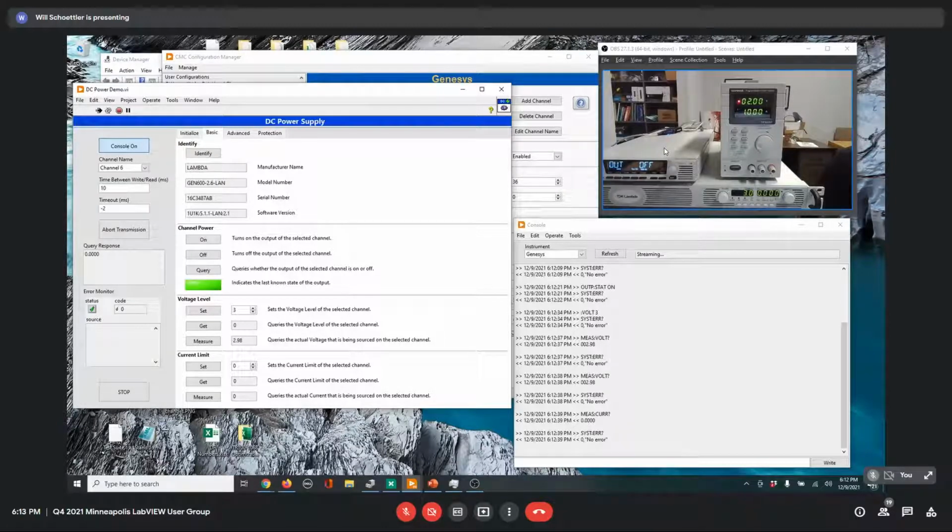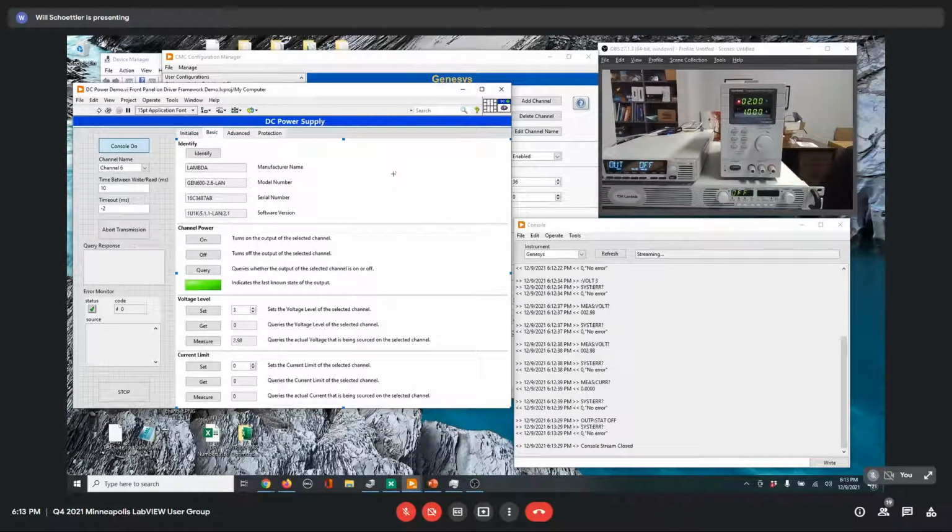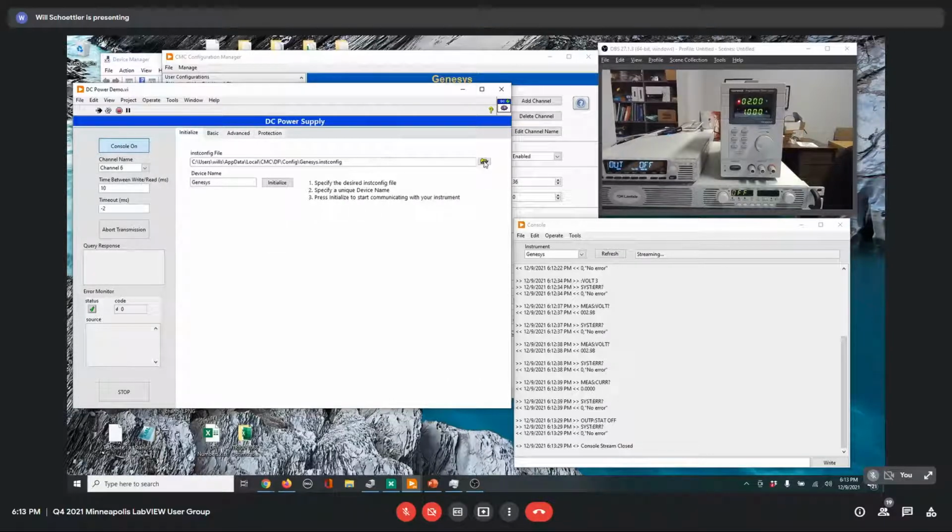All right, so let's say something else happened in this situation. Maybe we chose the Genesys power supply, but because of the long lead times that we're seeing, we weren't going to receive it for a while. But we still wanted to make sure that our program was going to work properly with a different range of voltages or different noise or something like that. So actually we have simulators too that we can use in order to interact with our code without actually having anything connected. And it's the exact same process.